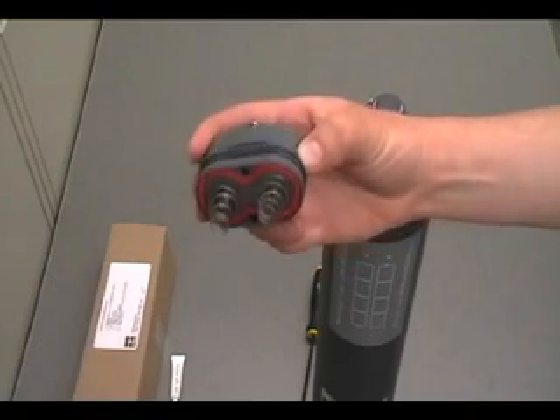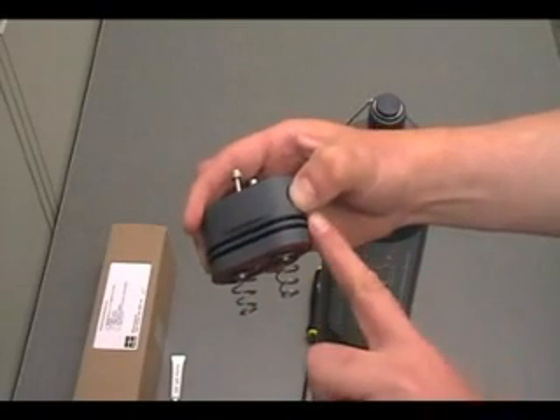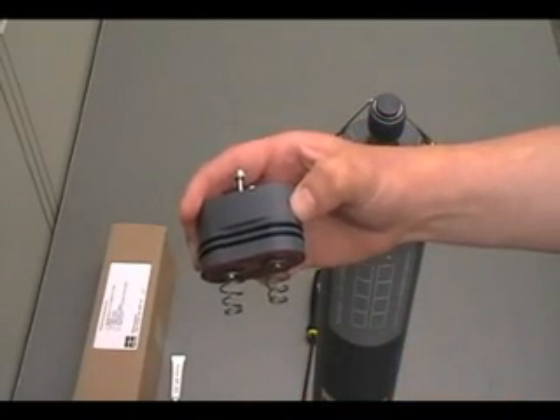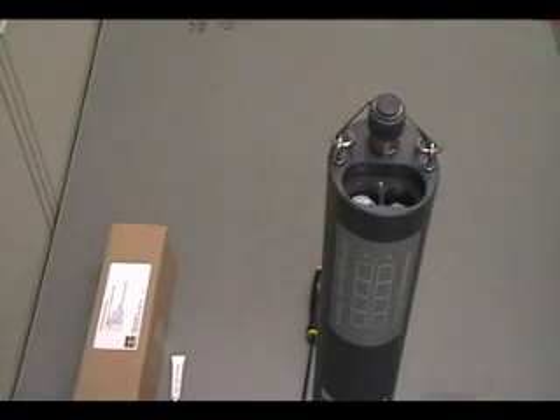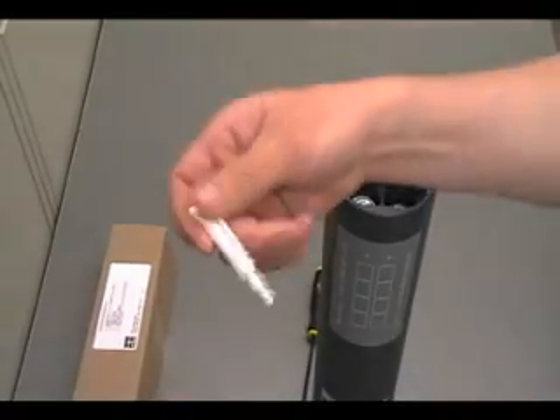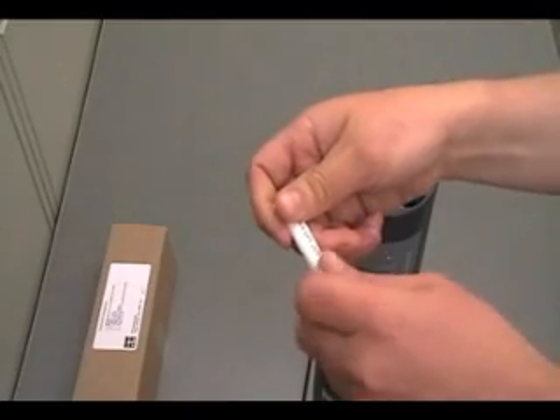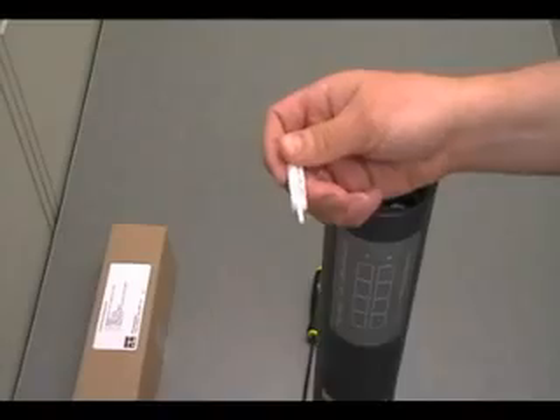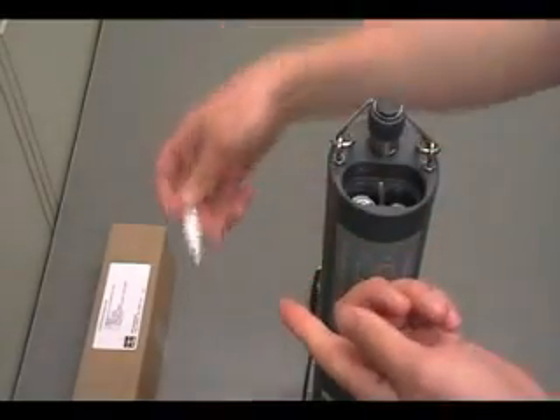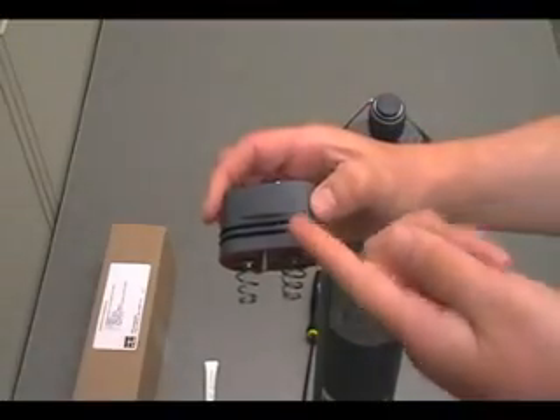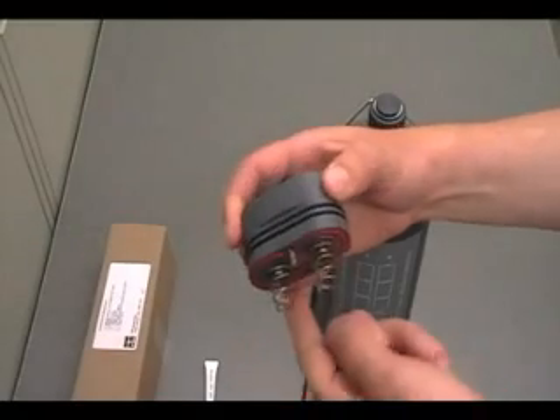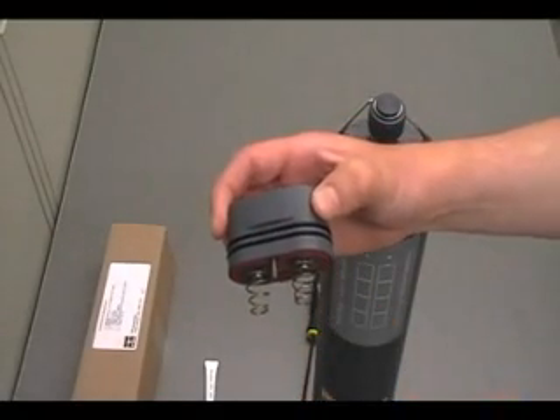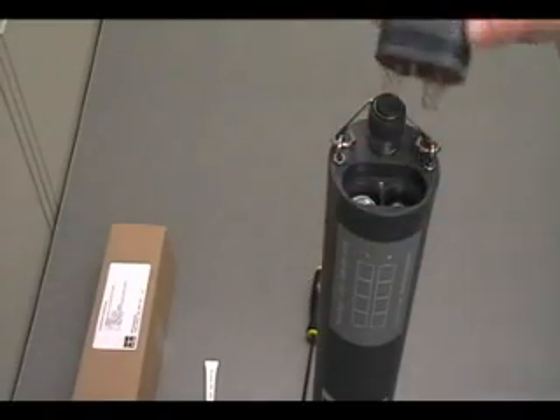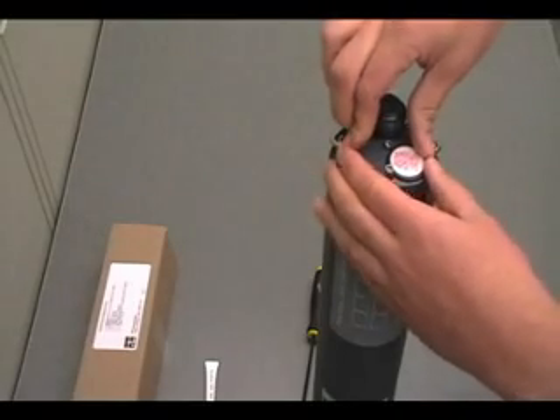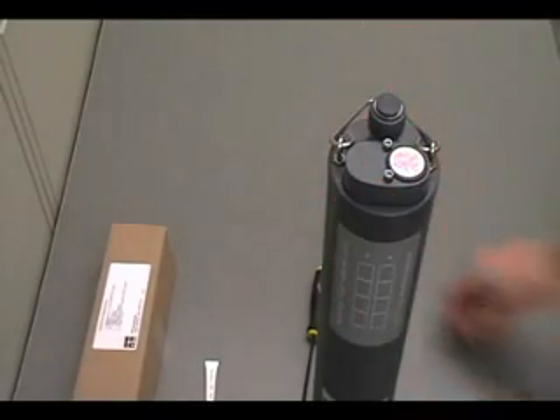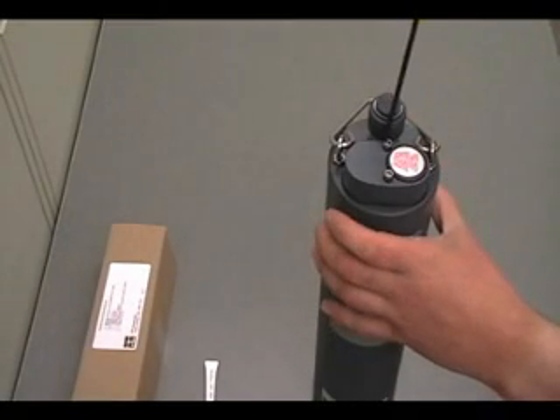Step 4. Make sure that the black O-rings that encircle the lid are completely clean. No dirt should be present on or under any of these O-rings. Apply a small amount of Krytox to the black O-rings so that they are shiny. Do not over-lubricate them. Step 5. Put the lid back on the battery compartment in the orientation shown. Push down to make sure it is seated properly. Tighten the screws until snug, but do not over-tighten the screws.